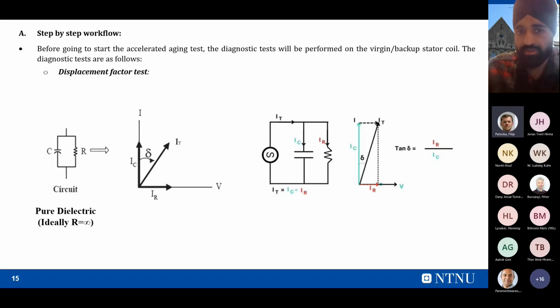But in an actual scenario, the resistive component of the insulation is present. Due to that, there will be some IR amount of current, and the net vector sum of IC and IR gives IT. So the current drawn from the source will be much higher compared to the previous scenario. Tan delta is perpendicular by base, so IR divided by IC. If IR is huge, then the tan delta value is huge, which means that if there are some defects, or the resistance is not infinite, then IR current will be there, which ultimately causes tan delta. So we want the tan delta value to be low. It should not be higher.